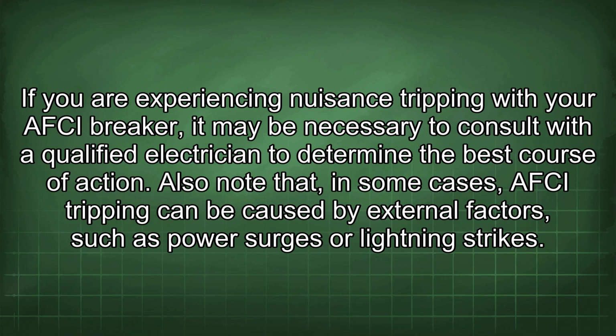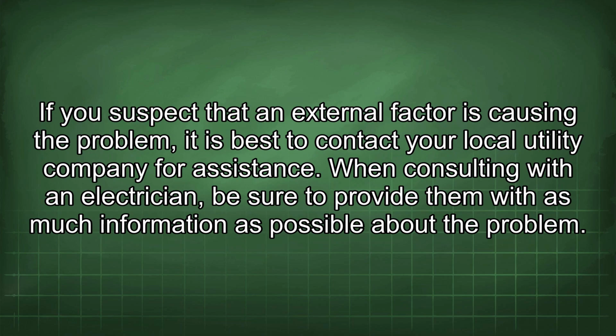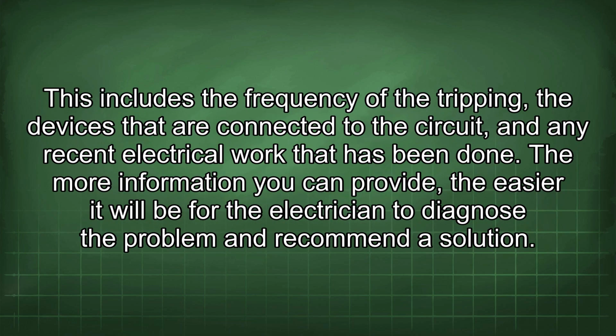Also note that, in some cases, AFCI tripping can be caused by external factors, such as power surges or lightning strikes. If you suspect that an external factor is causing the problem, it is best to contact your local utility company for assistance. When consulting with an electrician, be sure to provide them with as much information as possible about the problem. This includes the frequency of the tripping, the devices that are connected to the circuit, and any recent electrical work that has been done. The more information you can provide, the easier it will be for the electrician to diagnose the problem and recommend a solution.